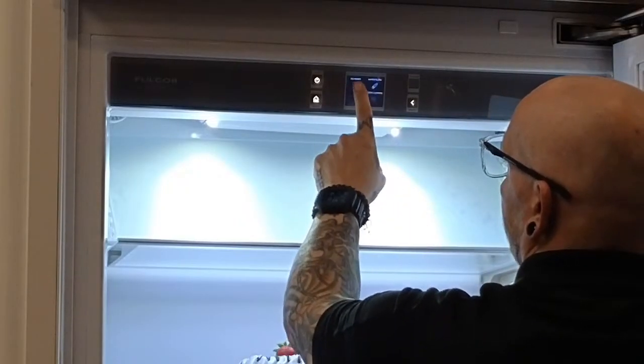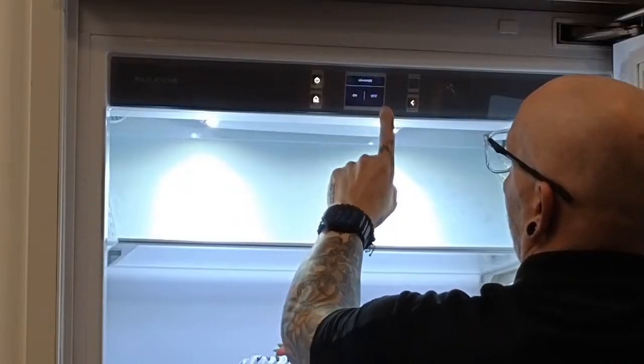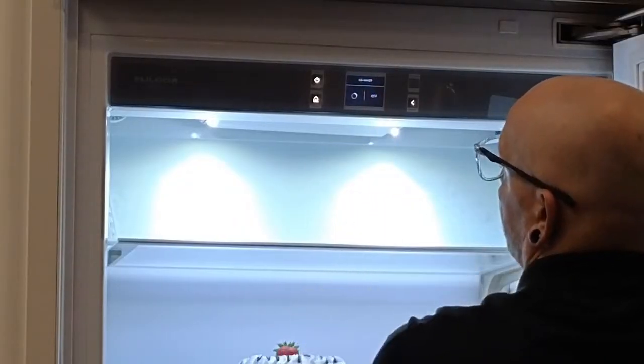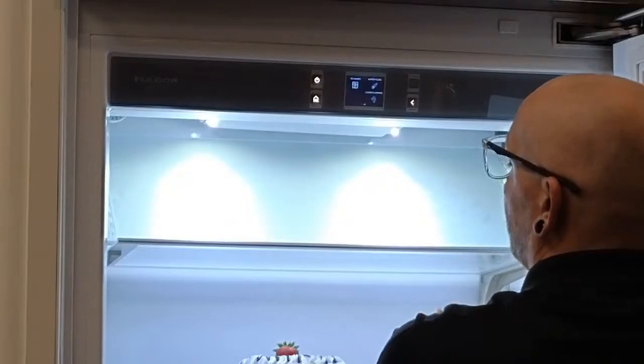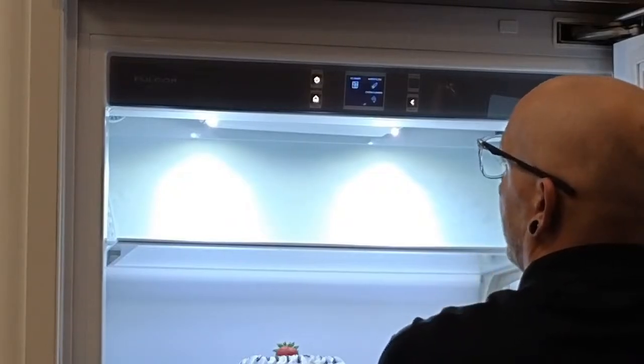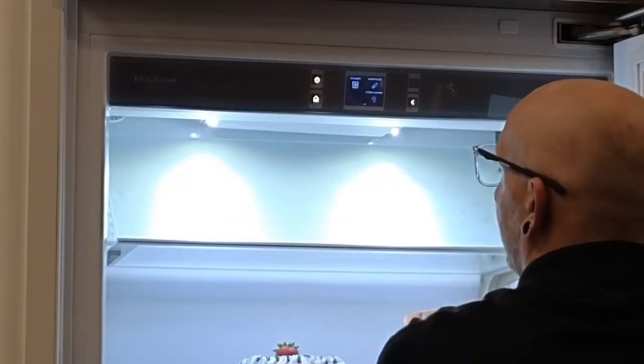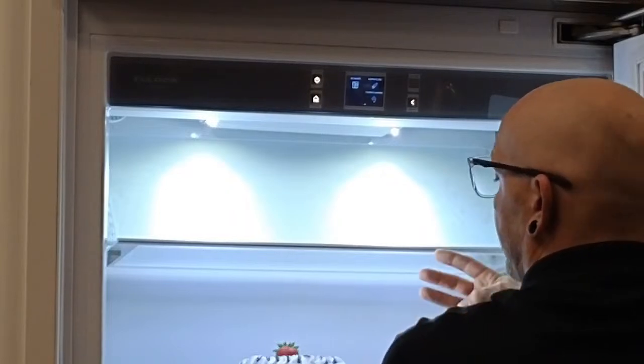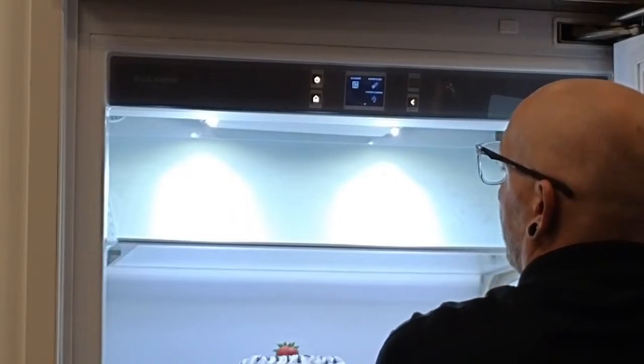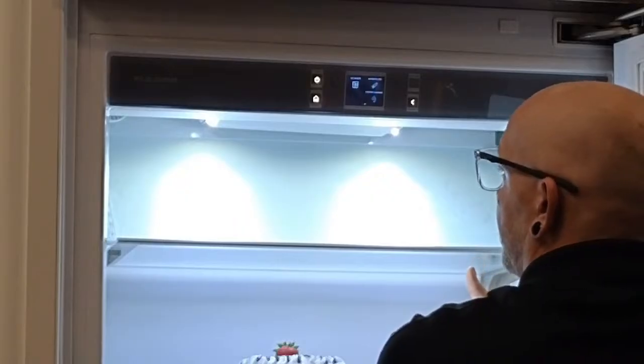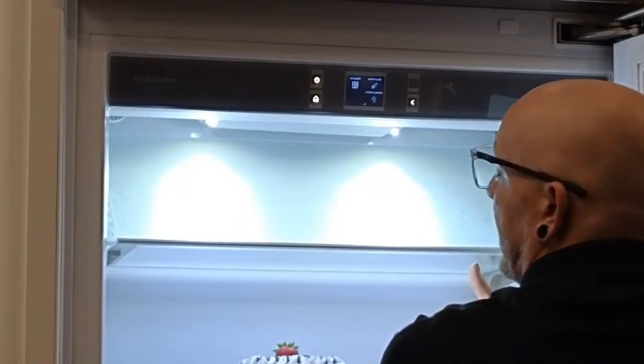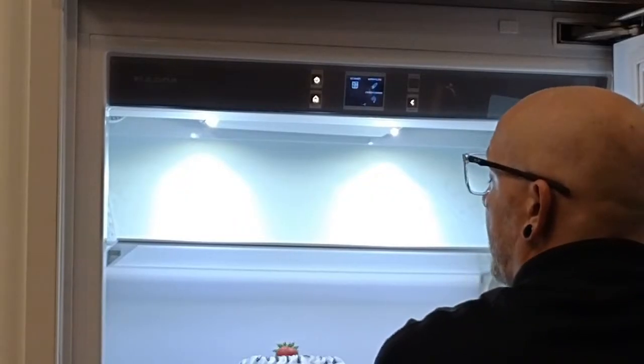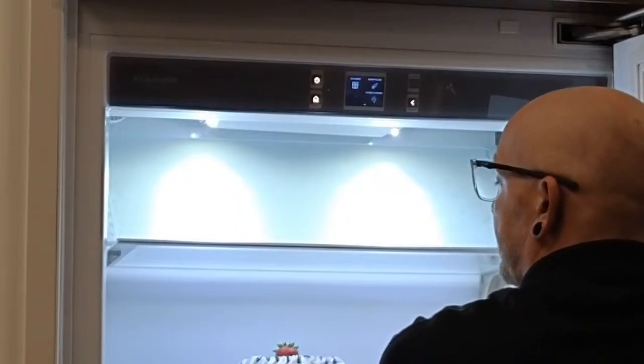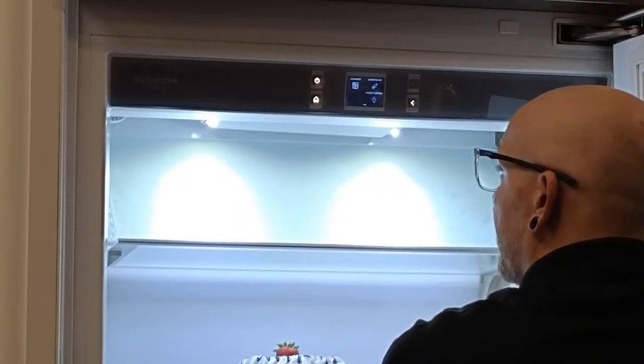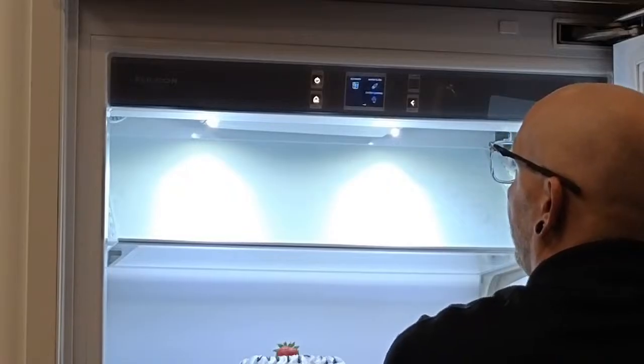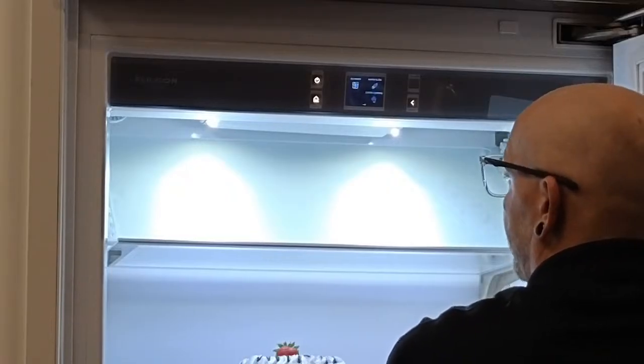To run system cleaning, you must turn ice maker off. This is the only way that you can run this system cleaning. This is pressurizing the system. This is going to test your ice maker, your water valves, and the communication between your electronics and your ice maker. So if the customer has no ice, no errors, or they have an error code that has like no water in and they're not making any ice, you can run this test and see if you've got function from the ice maker and see if you've got fill from the fill valves themselves and water supply from the water supply.